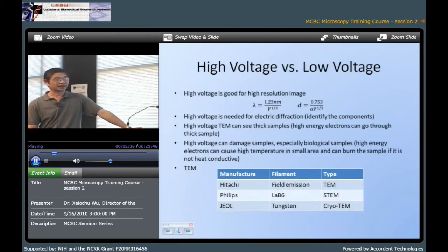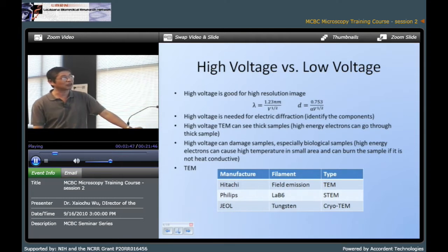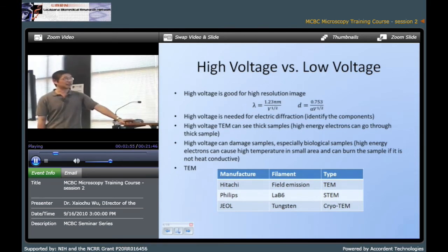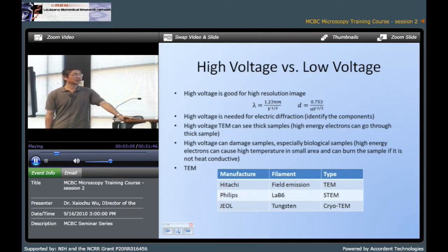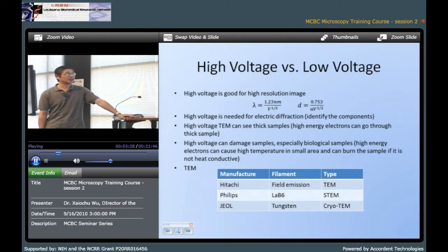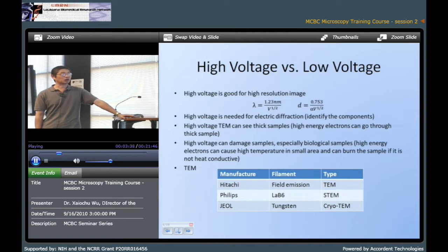Some people like to use high voltage and some say high voltage is not good. Some people like high voltage because, as we know from the equation, if the voltage is high then the resolution increases; if the voltage is lower, the resolution is not very high. Also for materials science research they prefer to use high voltage because with high voltage they can see thick samples — especially for solid material research if they want to see electric diffraction, they have to use high voltage. But high voltage also causes damage, especially to biological samples, because the high energy electrons can cause high temperature in a small area and burn the sample.